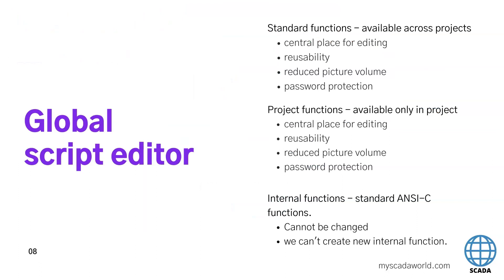The last option where we can put C actions is the global script editor. Inside here we can put some standard functions, project functions, and internal functions. The standard functions are available across the project — so anytime you create one standard function, you can use it in all projects you have on your computer. And if you want to change this function, you make this in the central editor and all functions you use in your project will be replaced.